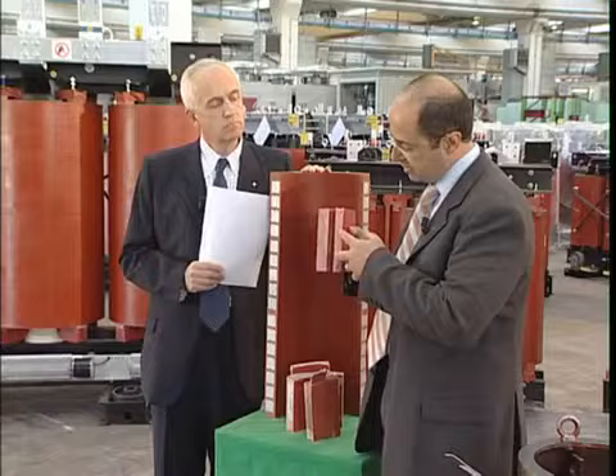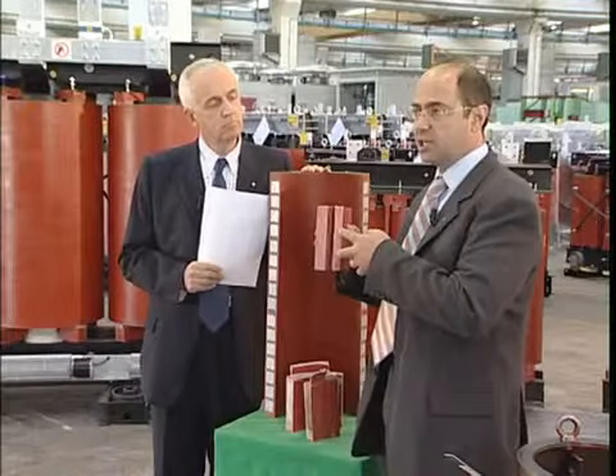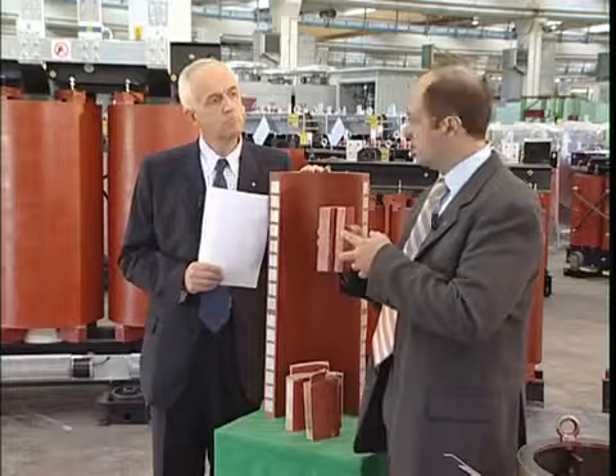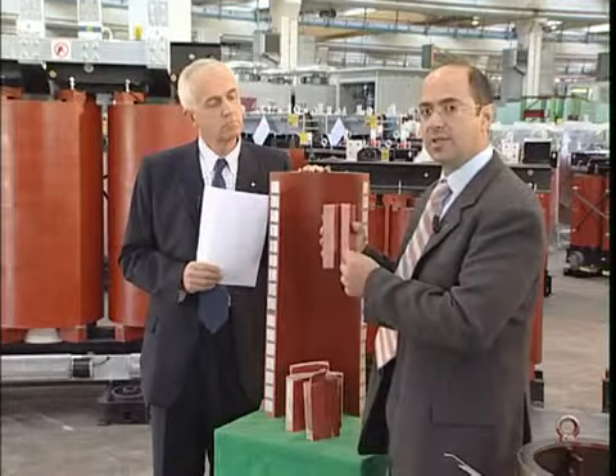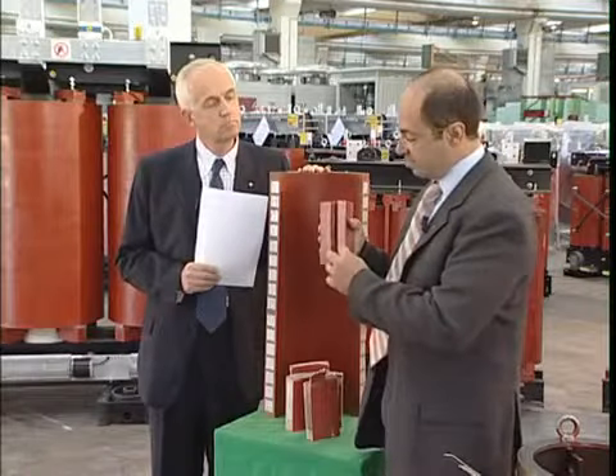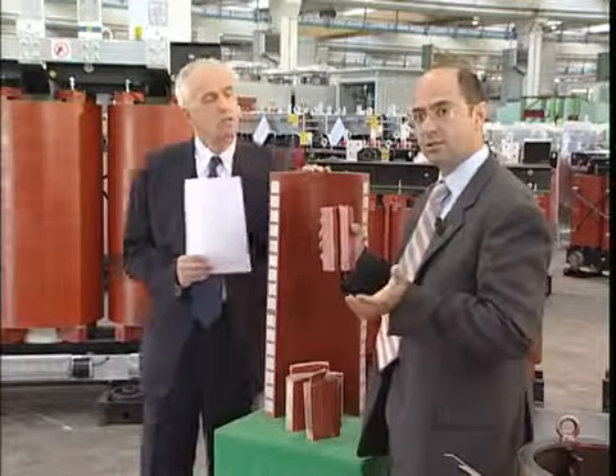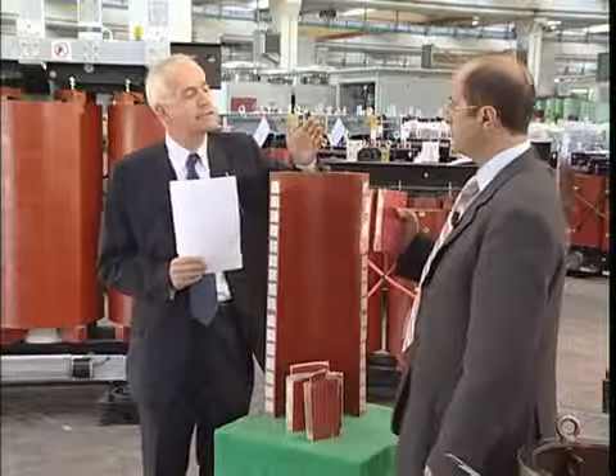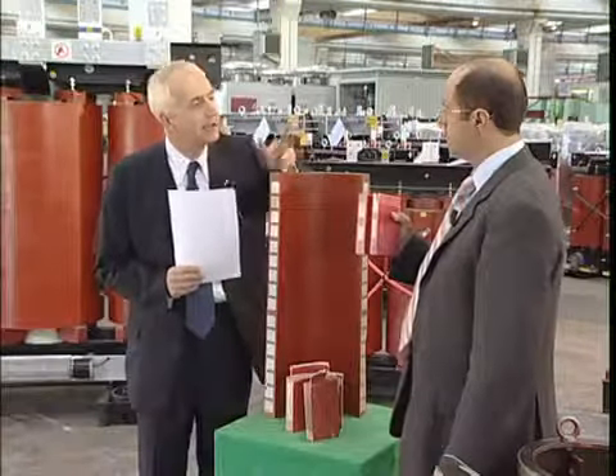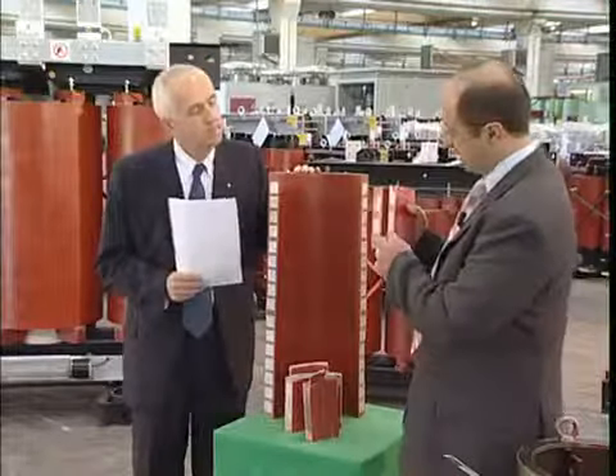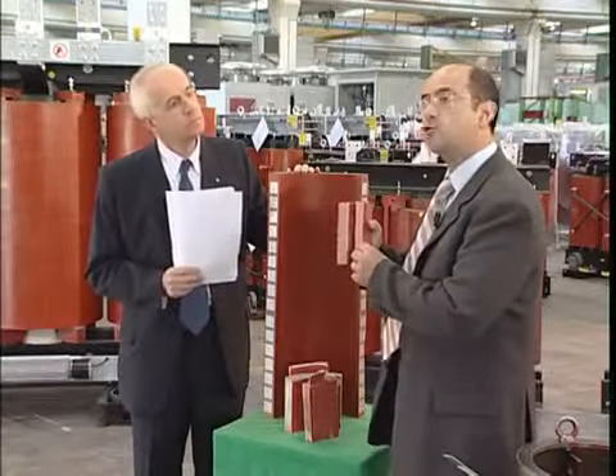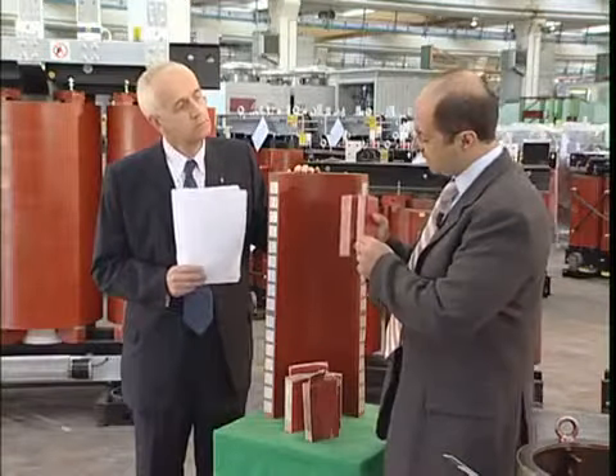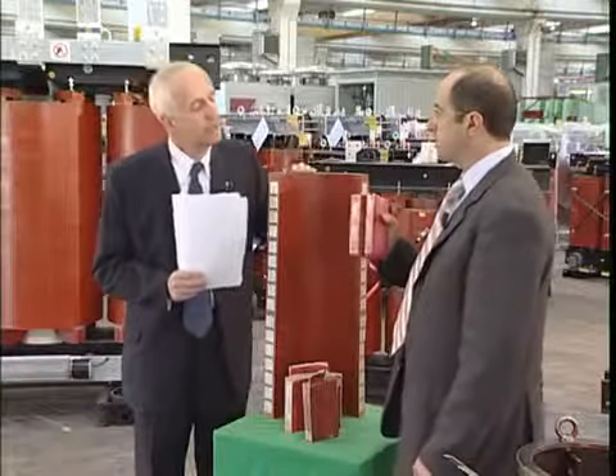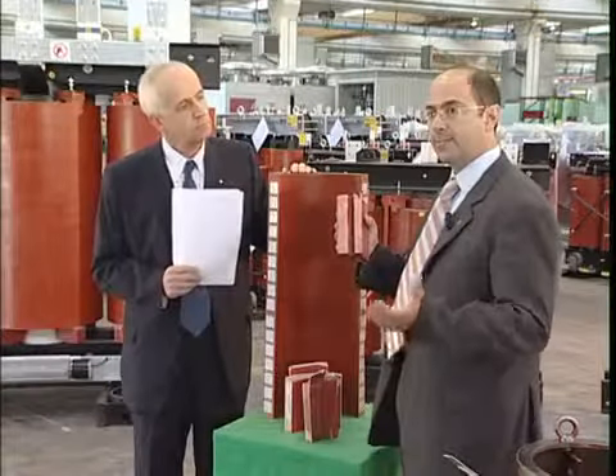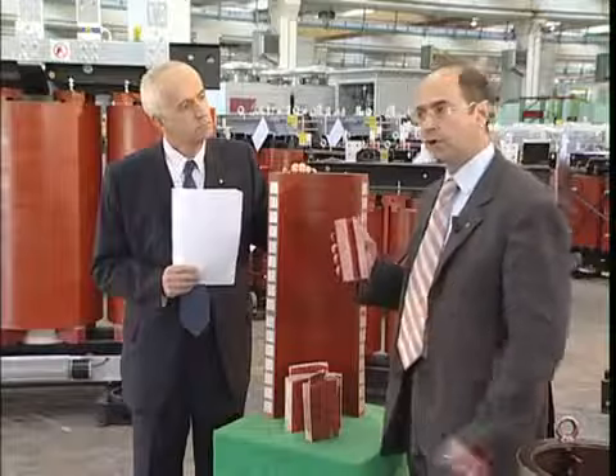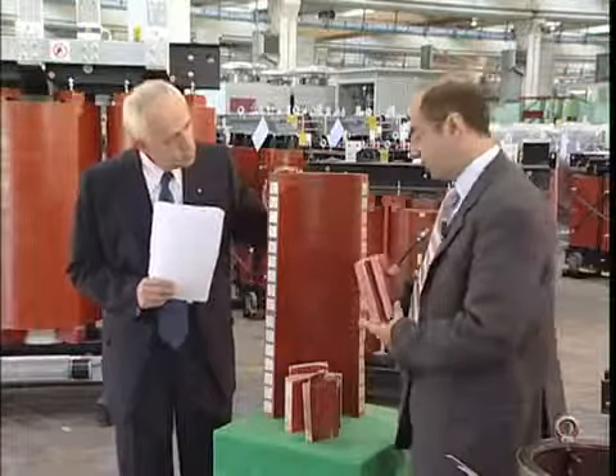Why? Because the turn voltage of one layer results in a voltage at the layer ends which is 10, 15 or 20 times the turn voltage, while between the various layers, i.e. in the radial direction, the potential difference between the two conductors is a few dozen times the turn voltage. We can therefore say that insulation is constant, but the dielectric stress and the applied voltage are not constant at all. As a consequence, the insulating material installed between the two layers ages in a different way compared to the insulating material installed elsewhere. What does this aging lead to in the long term? In the long term, this reduces the material's insulating properties and consequently results in the transformer's death. A short circuit? A short circuit between the turns.